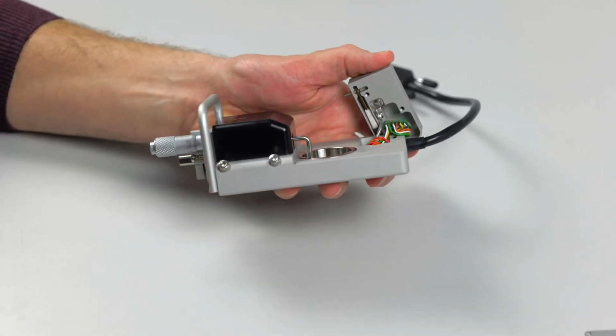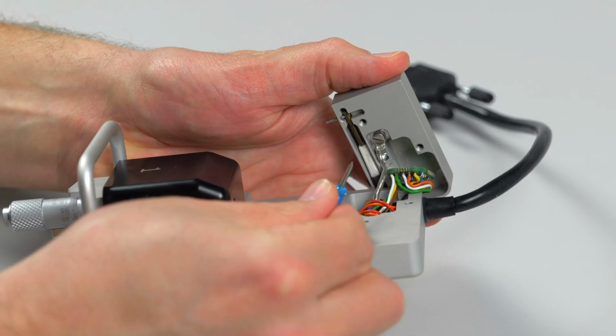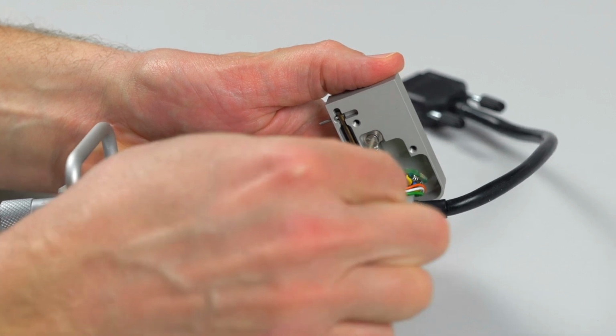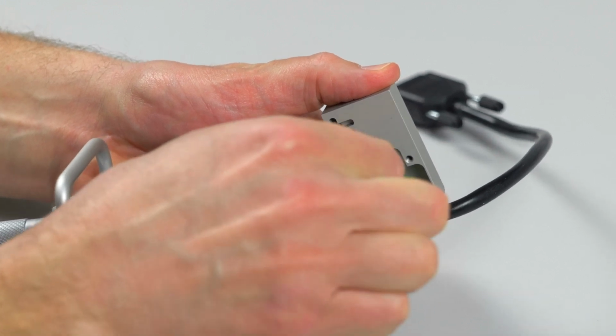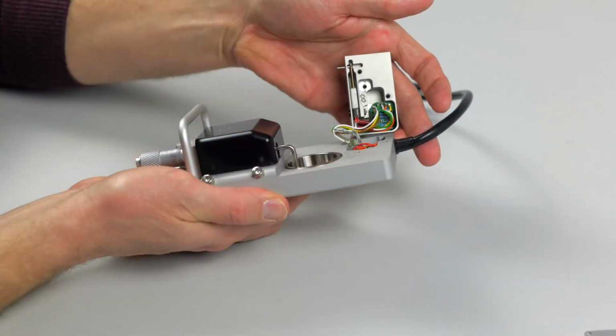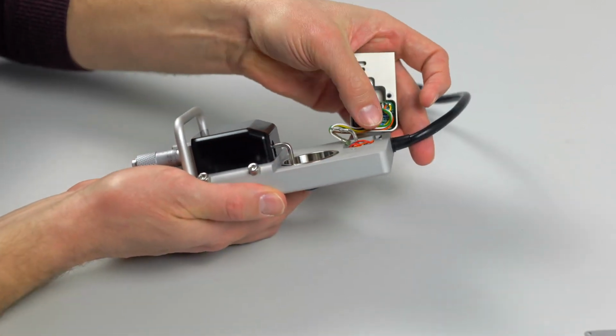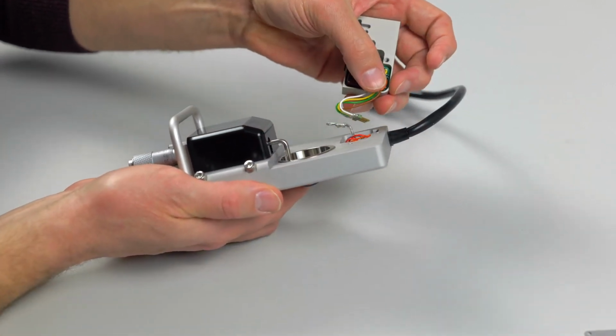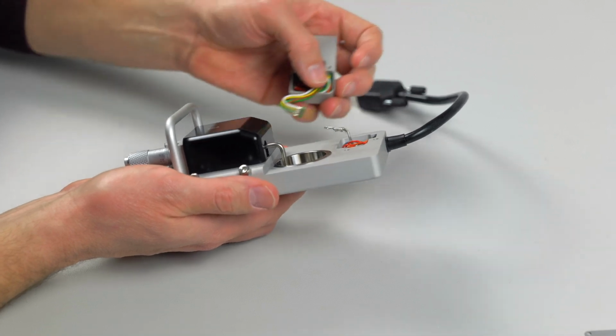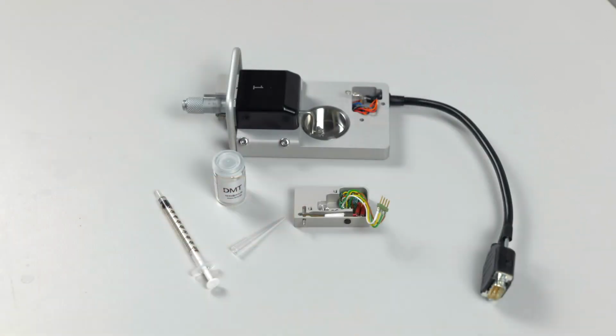There's an additional screw inside the transducer housing which you will need to use your flathead screwdriver to remove. Once all screws are disconnected, carefully remove the transducer and be careful not to pull too hard as there are delicate wires attached. Once the old transducer is removed, it's time to prep the new transducer for use.